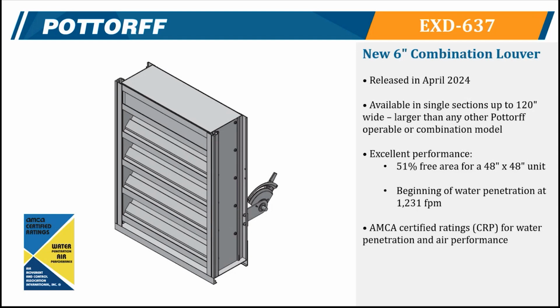The big thing with this is primarily the section size, that was the driver behind doing this as a project. We do have a couple other 6-inch combo louvers that are pretty good, but they're more limited in the width of sections you can get. This will go single sections up to 120 inches wide. We've got a stronger fixed blade, which allows more stiffness to the section, which allows that larger section width. This is the largest of any of our combo models among louvers.